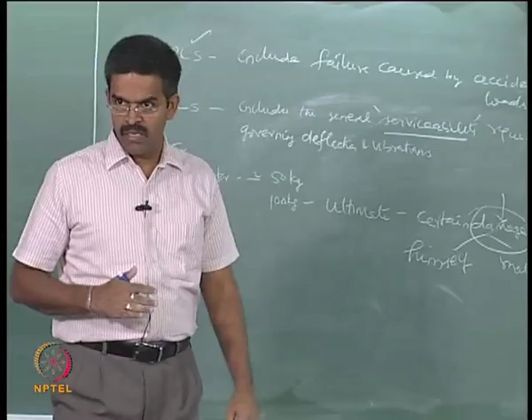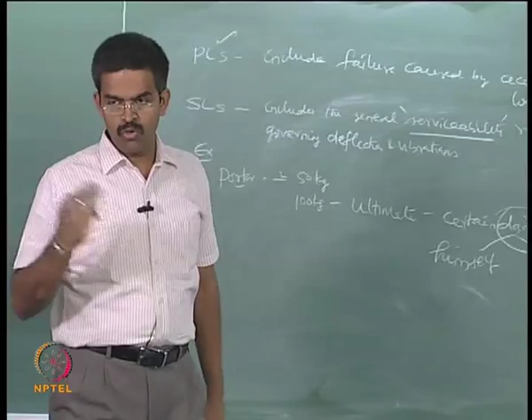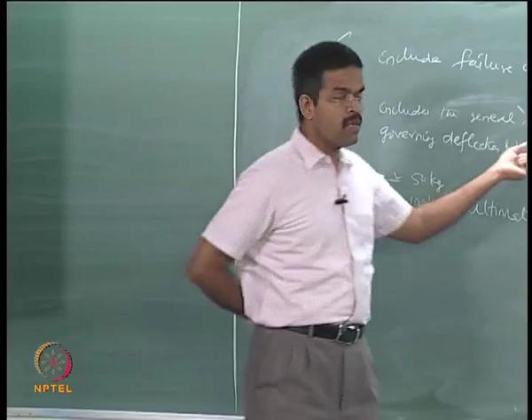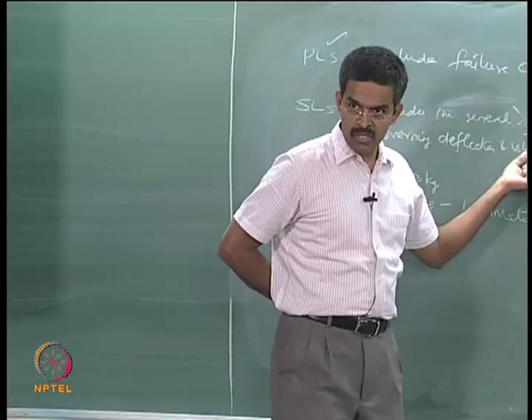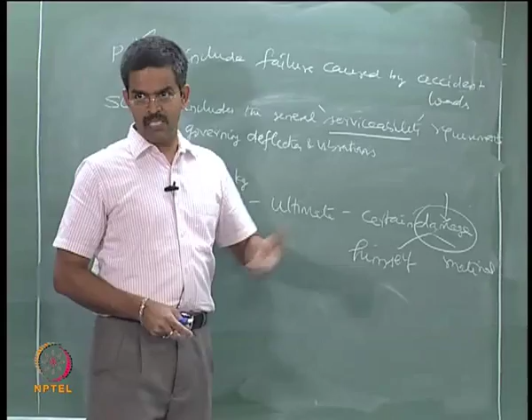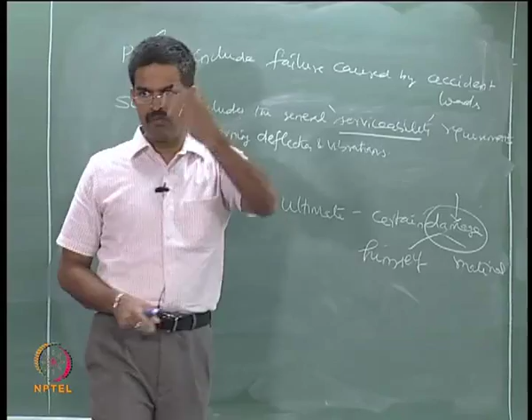In terms of vibration, the platform deck vibration should not cross 0.05 G, that is 0.05 of 9.81, etc. Why? Because this will cause a lot of secondary mass activity on my machinery. I keep a machine on a table which is static, operate the machine, performance of the machine is x in terms of its efficiency. I put the machine on a vibrating platform, vibrate the platform horizontally and vertically, very high value, and operate the machinery, performance is y. You will see efficiency y will be much lower than x. So I do not allow that vibration to happen in my platform deck, at least in heave direction or in yaw direction, whatever may be the degree of freedom we are discussing.